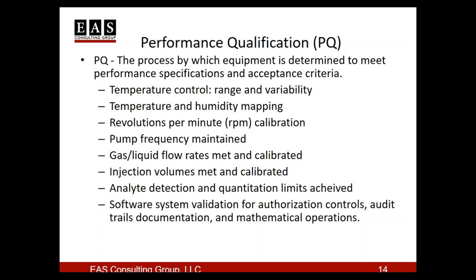Software validation is also very, very important. Software has to be compliant with 21 CFR 11, which covers electronic records and electronic signatures. That means there's audit trail documentation and all the mathematical operations being performed have been verified to be correct. And then there are authorization controls in place so that we know who is using the instrument at all times.